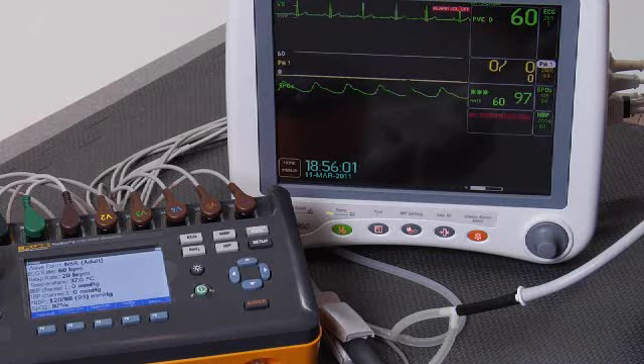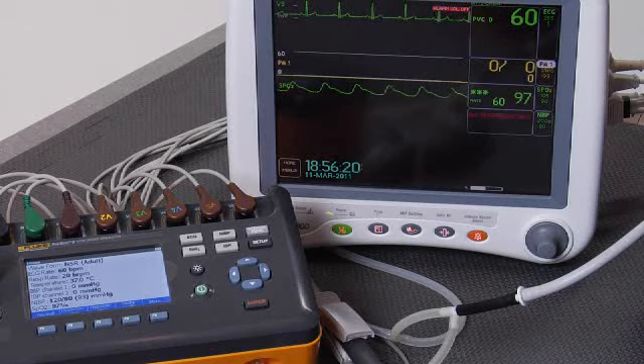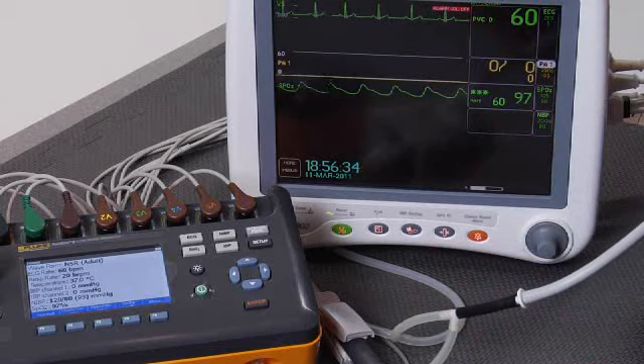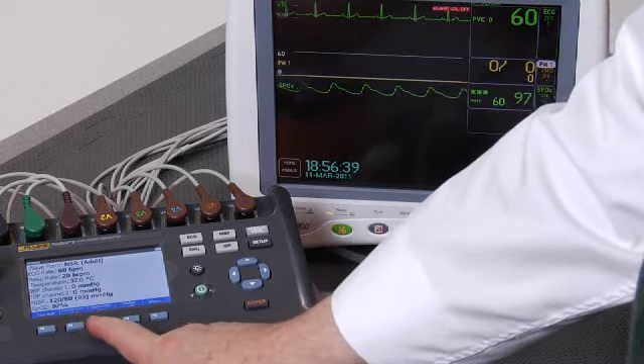We'll do hypertensive first, followed by normal, followed by hypotensive, in order to assess whether we have a performing patient monitor. We will compare the displayed values on the ProSim 8 against what's displayed on the patient monitor at each set of simulated parameters. Let's begin now. First thing I'm going to do is zero P1, and it is at zero. Now I'm going to pick hypertensive.